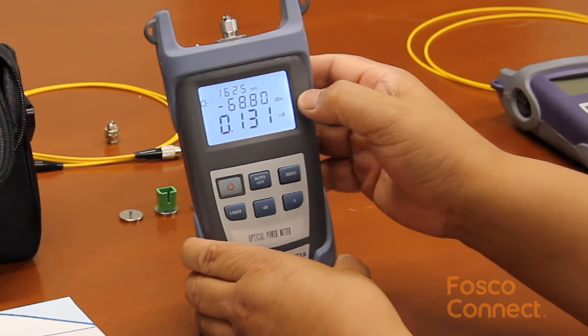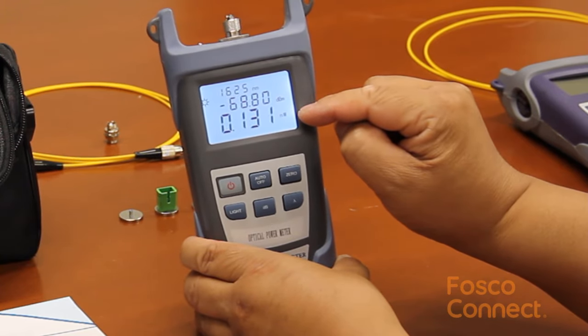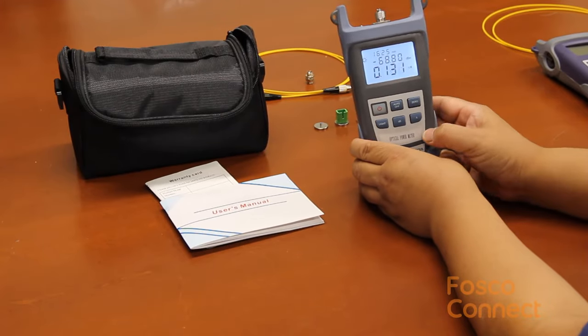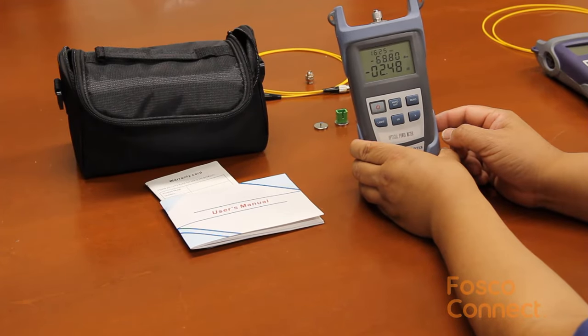It shows a power measurement in dBm on the second row and nanowatt on the third row. So let's use a laser light source to test a fiber jumper cable.